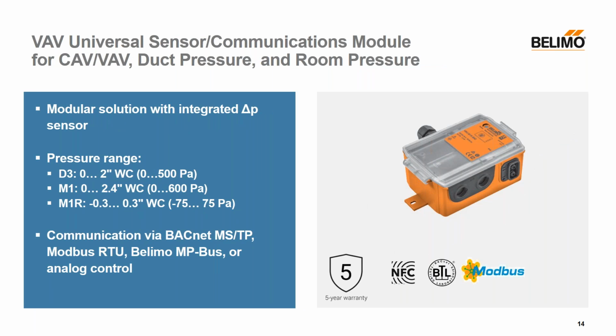Next, we have our VAV Universal Sensor Communication Module. This accessory is to be placed into a duct to create a pressure differential that can be read by the VAV compact actuators. We can combine this with the damper actuator, optimally suited for VAV, CAV, room pressure, or duct pressure applications. We offer a few different pressure ranges, and it can communicate via BACnet MSTP, Modbus RTU, Belimo MP bus, or analog control.